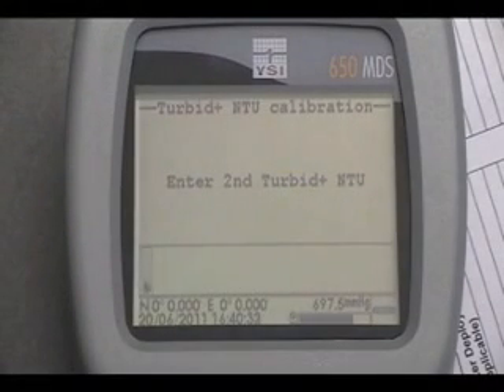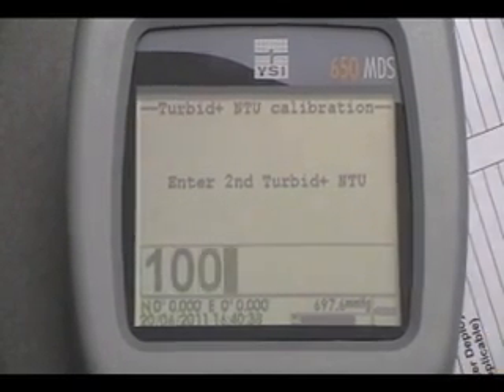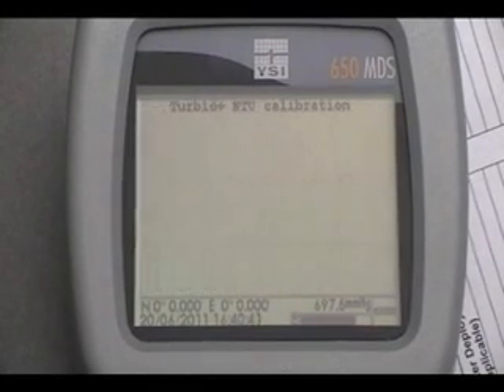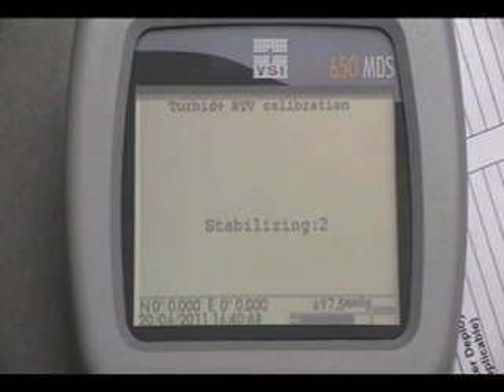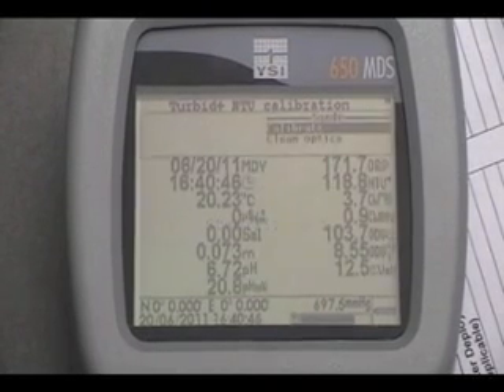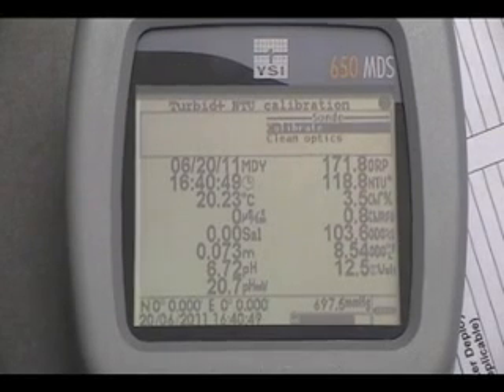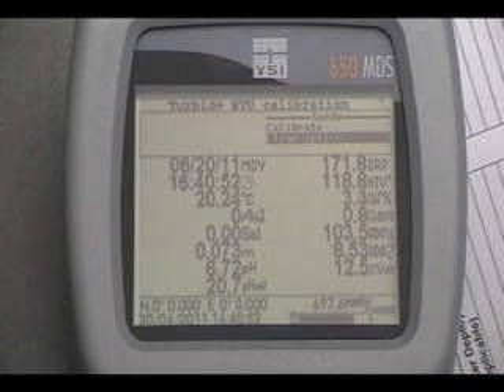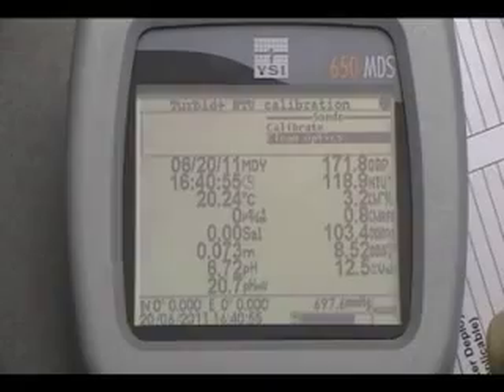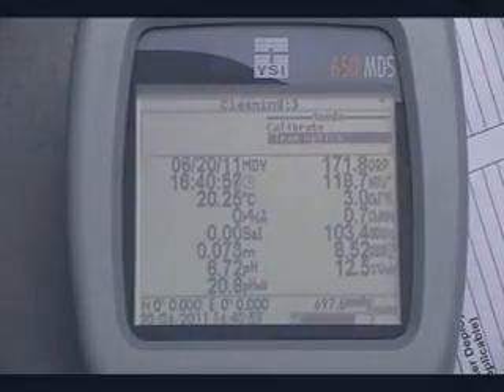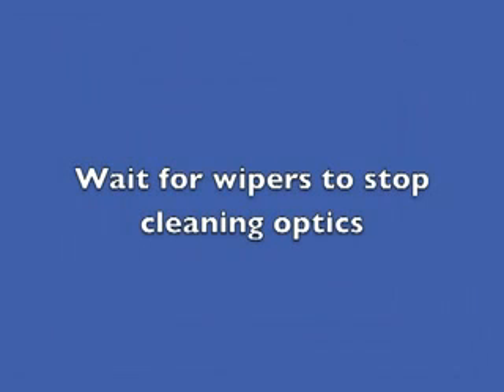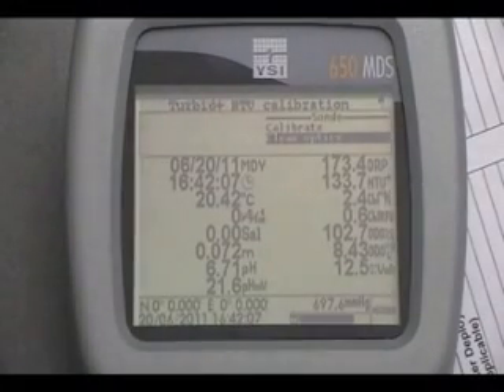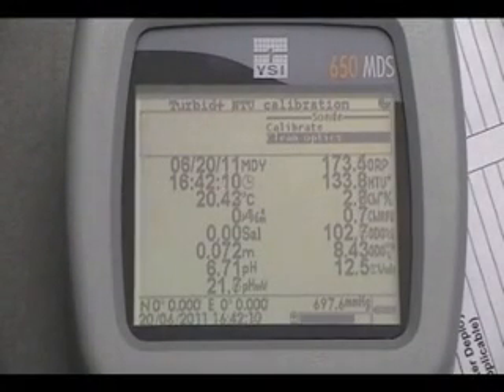Step 15. Input the value 100 at the prompt and press Enter. The screen will display readings. Step 16. Activate the sensor wiper 1 to 2 times by pressing Clean Optics. Step 17. When the readings have stabilized, record the pre-calibration turbidity reading for 100 NTU on the calibration worksheet.